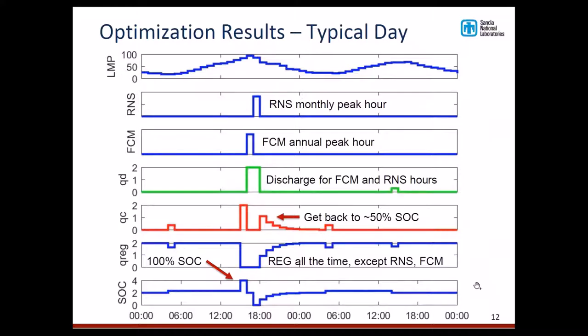This is a closer look at what happens during that peak hour. In this case, the peak for the forward capacity market is a different hour than the RNS peak, and they're right next to each other. So you charge up to 100% state of charge right before those two hours happen, then discharge to capture both peaks. After that, you get back to 50% state of charge and start doing frequency regulation again.